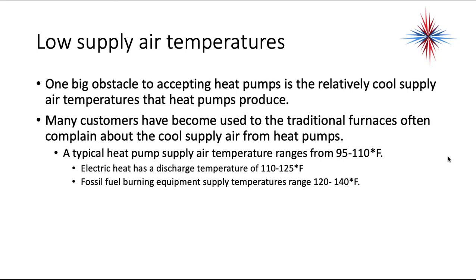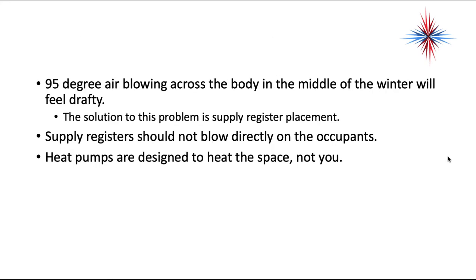The biggest obstacle to accepting heat pumps by customers is the relatively cool supply air temperatures that heat pumps produce. Many customers have been used to traditional furnaces, and they often complain about cool supply air from heat pumps. A typical heat pump supplies air temperatures from about 95 to 110 degrees. Electric heat has discharge temperatures from 110 to 125 degrees, and fossil fuel burning equipment like oil or gas supply temperature ranges from about 120 to 140 degrees. 95-degree air blowing across the body in the middle of the winter will feel drafty. The solution to this problem is proper supply register placement. Supply registers for heat pump systems should not blow directly on the occupants. Heat pumps are designed to heat the space, not you.